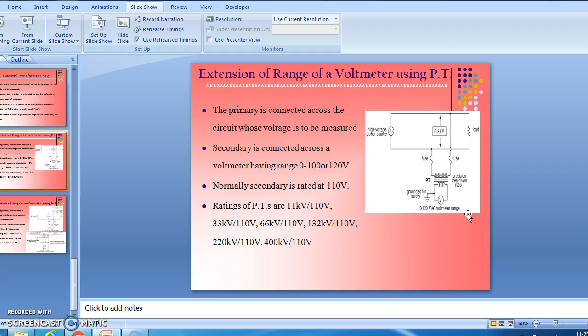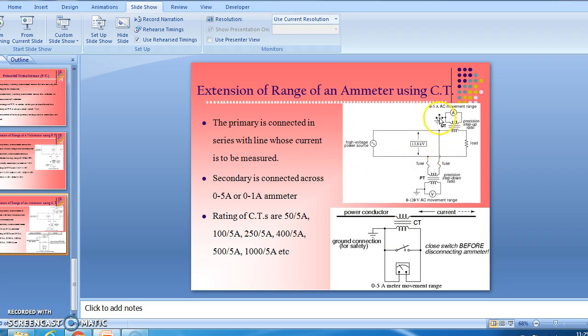This is how we can extend the range of a voltmeter using a PT. The primary is connected across the circuit whose voltage is to be measured, and the secondary is connected across a voltmeter with a range of 0 to 100 volts or 120 volts — normally the secondary is rated at 110 volts. Similarly, we can extend the range of an ammeter using a CT, where the primary is connected in series with the line and the secondary is connected across an ammeter with a range of 0 to 5 amperes or 0 to 1 ampere.